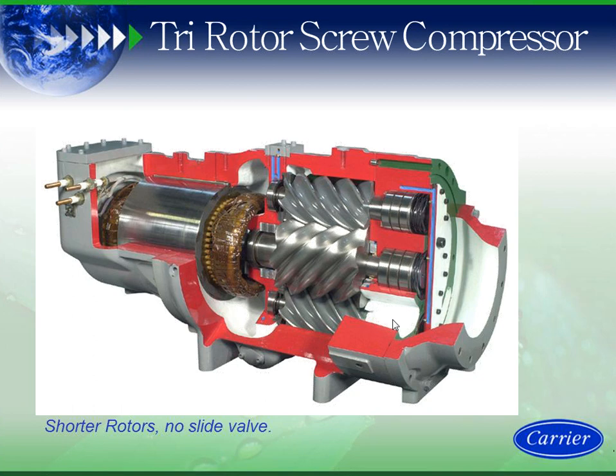If you talk to folks who don't like screw compressors, they're going to tell you a couple reasons why. They're going to say, A, I don't like the maintenance on the machine because of slide valves. Well, we eliminated the slide valve. And the other thing they're going to say is, I don't like the high-pitched scream of a screw compressor. This is actually quieter than a centrifugal. So this is a very quiet machine, and it's a very robust machine. And if you look at that compressor, it is built like a tank.